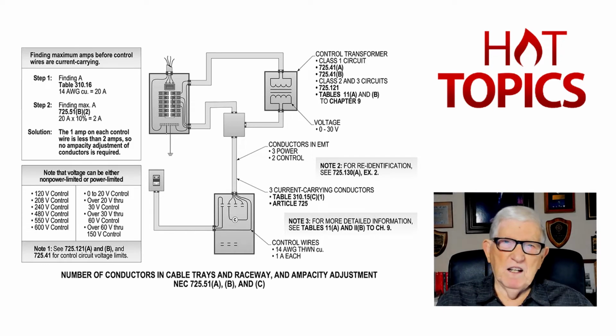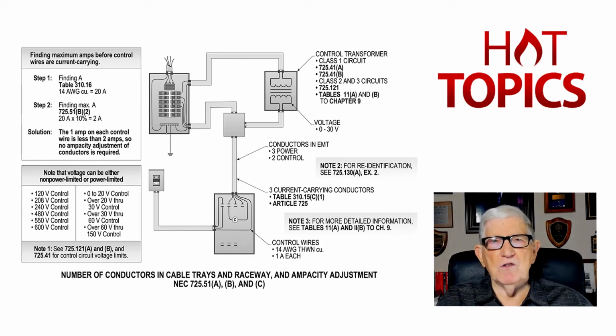You might get a little tingle, but it's a high impedance winding. It's just not going to give off enough energy to shock you real bad or create an arc that could burn you beyond a second degree burn, which OSHA does. They say, no, you can't be burnt past a second degree burn, even with your PPE on. So we pick all that information up in NFPA 70E and then OSHA 1910.331 through 333. You can pick all that information up to satisfy what we're talking about here.